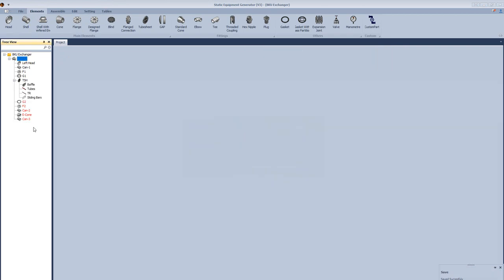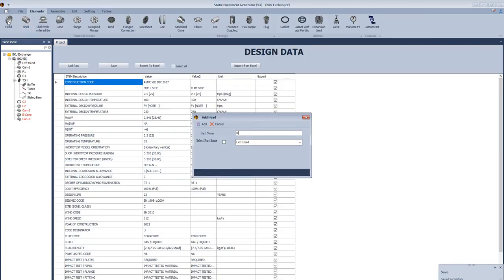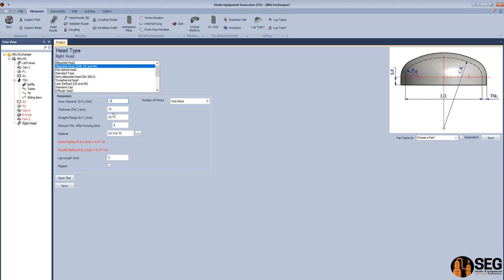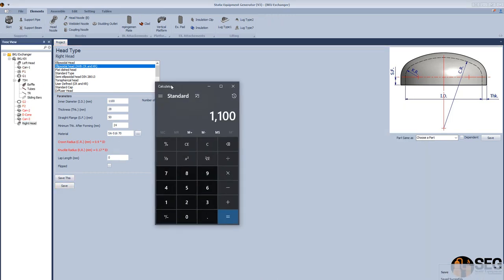Let's add another can — CAN3. Select the shell type, define the inside diameter, thickness, the longitudinal welding line orientation, the length, and click save. Let's add the last main part, which is the right head. Let's select ellipsoidal head with crown and knuckle radius. Define the inside diameter, the thickness, and the straight flange minimum thickness after forming. Now let's make a quick check for the crown and knuckle radius calculation. That's the crown radius and that's the knuckle radius.